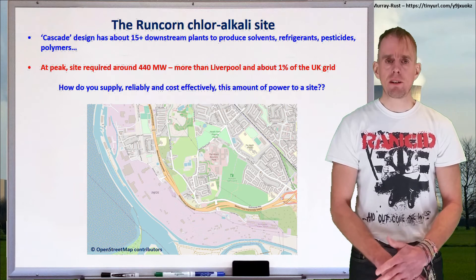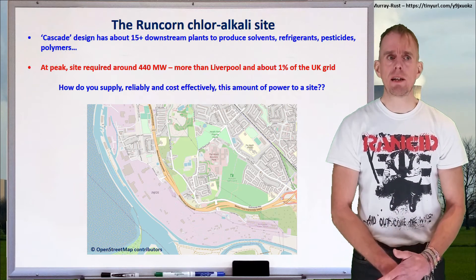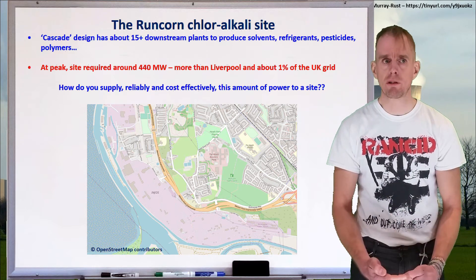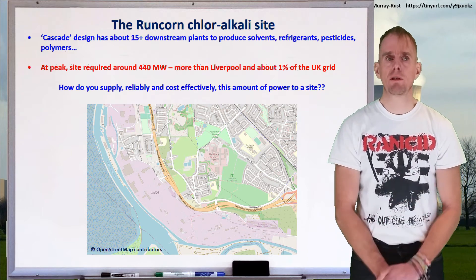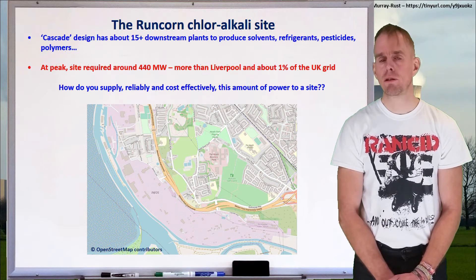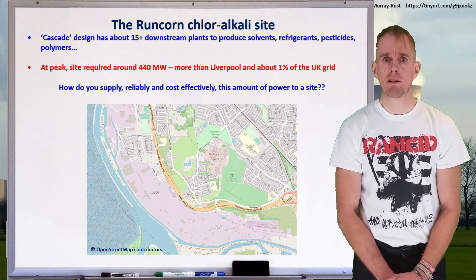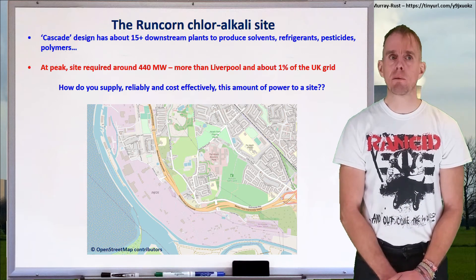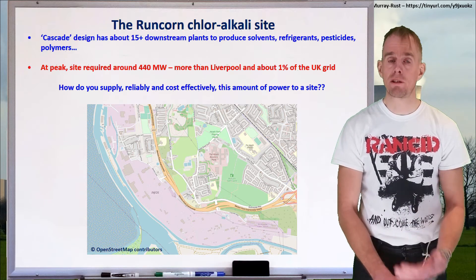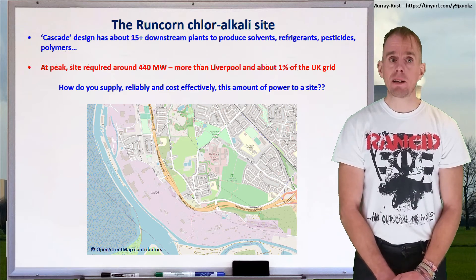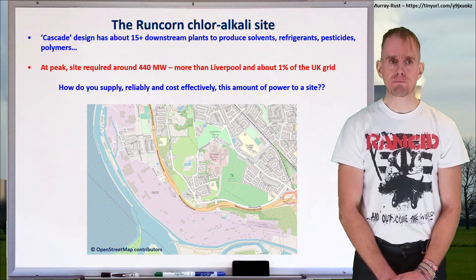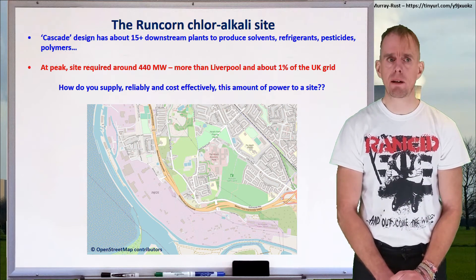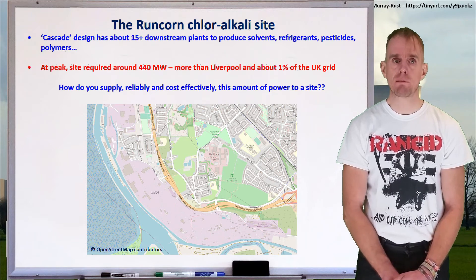The site has a cascade design: the chlorine cell rooms produce chlorine and caustic soda, with about 15 downstream plants producing solvents, refrigerants, pesticides, and polymers. At its peak, the site required about 440 megawatts of electrical power — more than the city of Liverpool nearby — which was roughly 1% of the UK power grid. The key challenge for electrochemical sites is how to supply this very large amount of power reliably and cost-effectively.